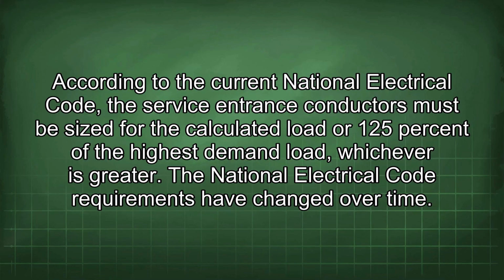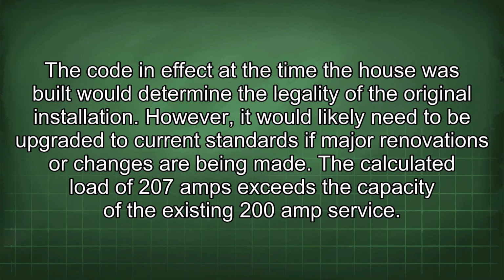According to the current National Electrical Code, the service entrance conductors must be sized for the calculated load or 125% of the highest demand load, whichever is greater. The National Electrical Code requirements have changed over time. The code in effect at the time the house was built would determine the legality of the original installation. However, it would likely need to be upgraded to current standards if major renovations or changes are being made.